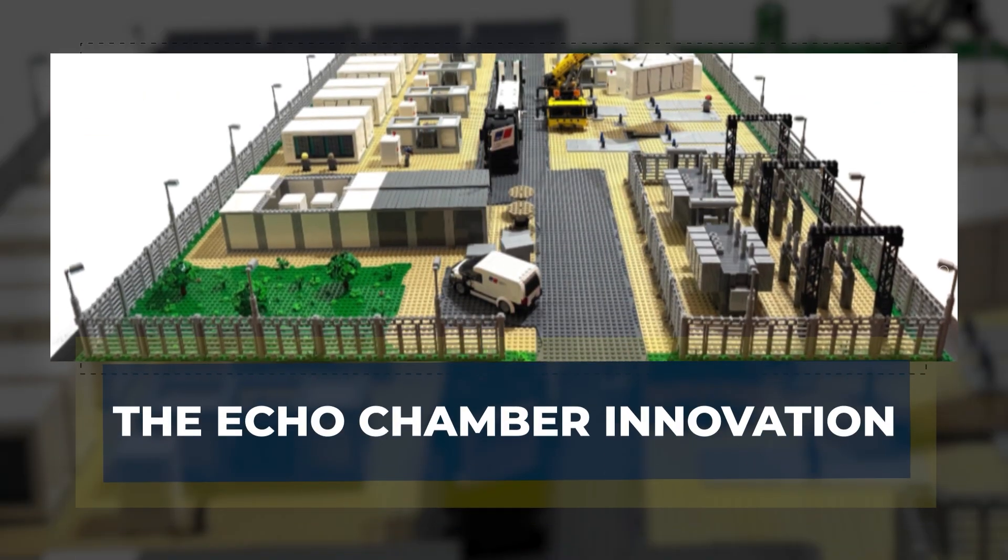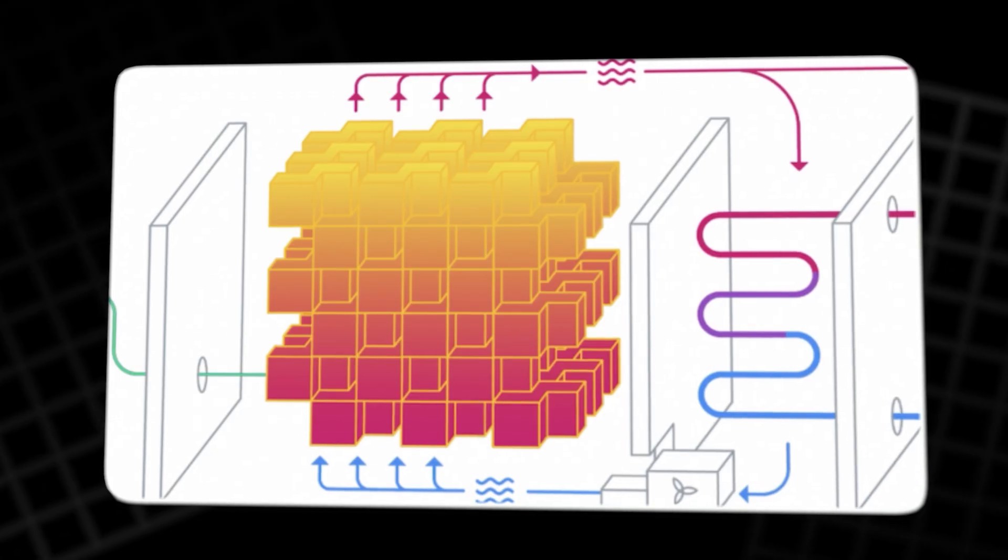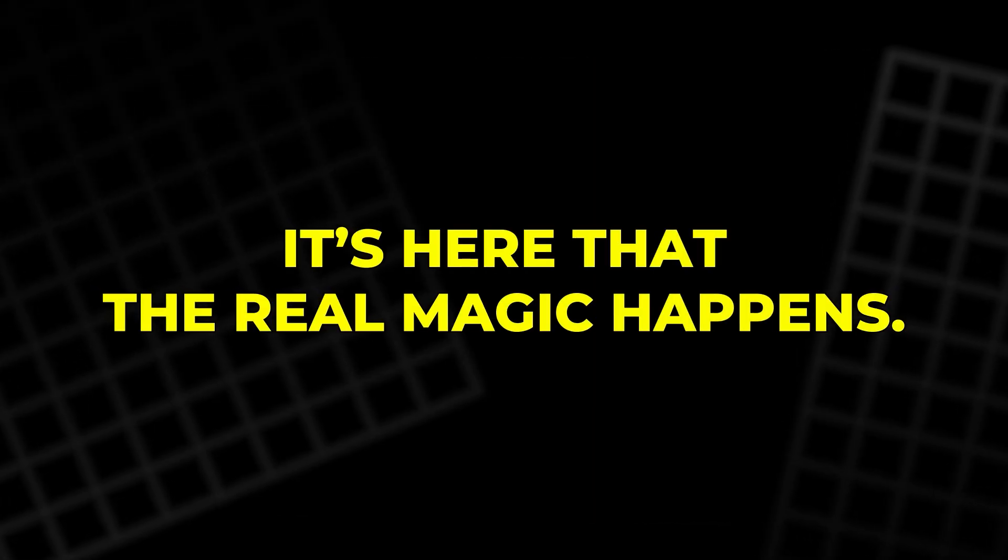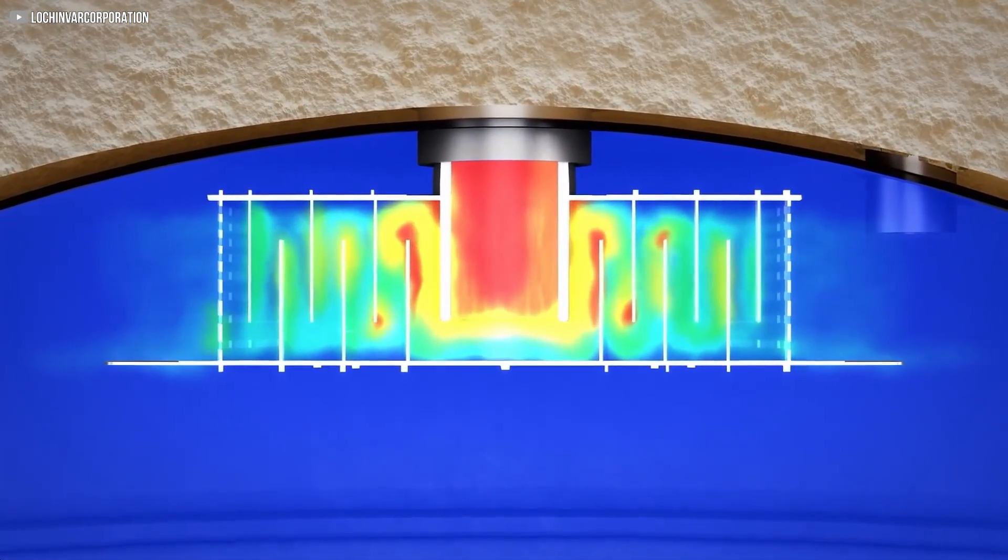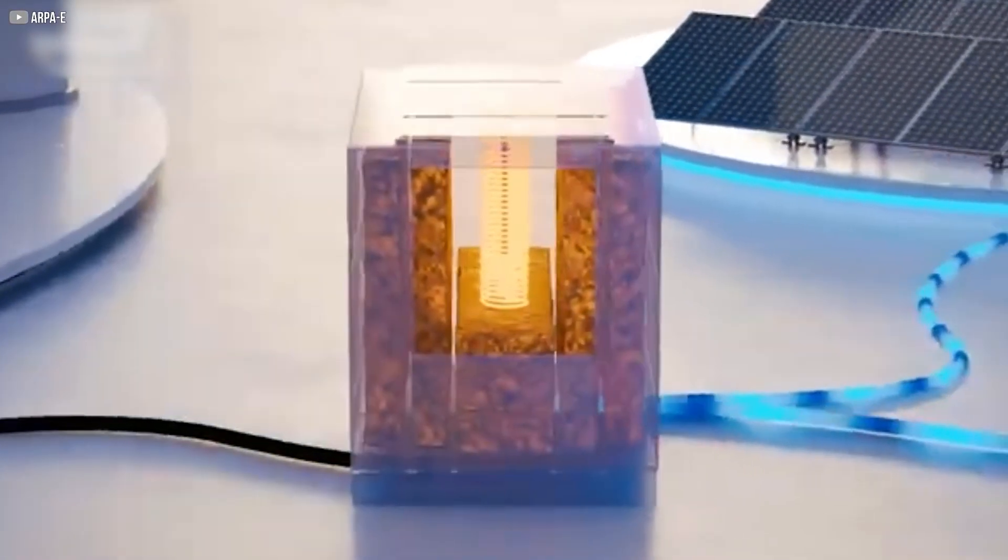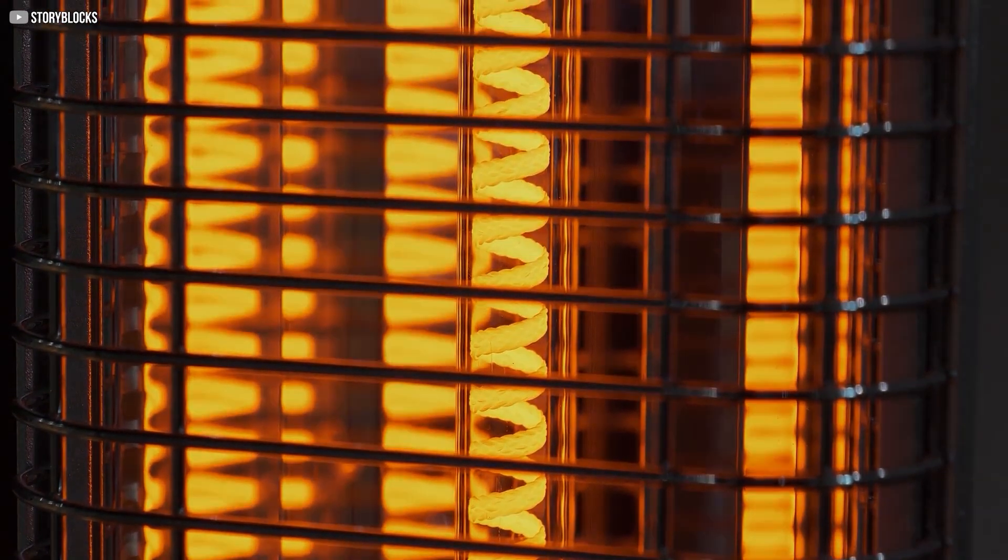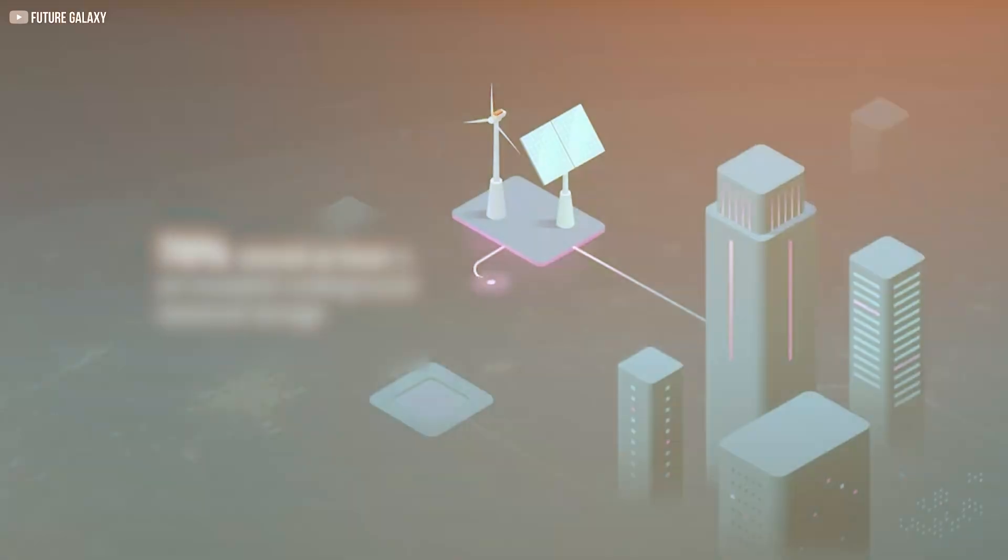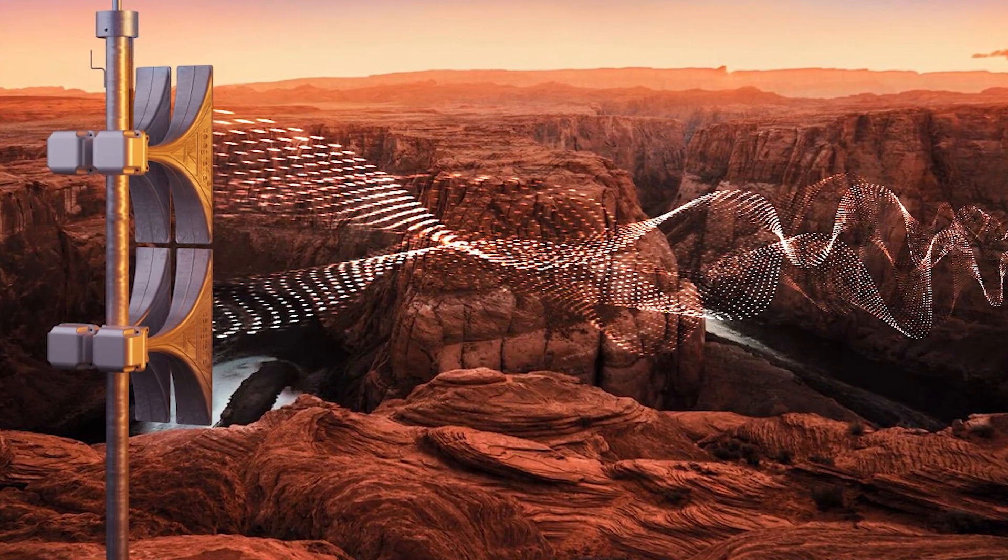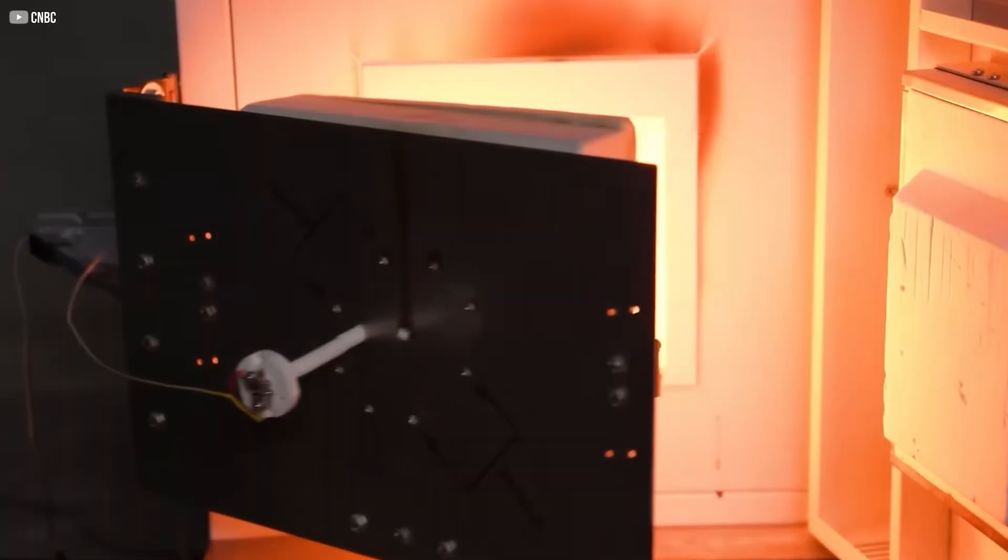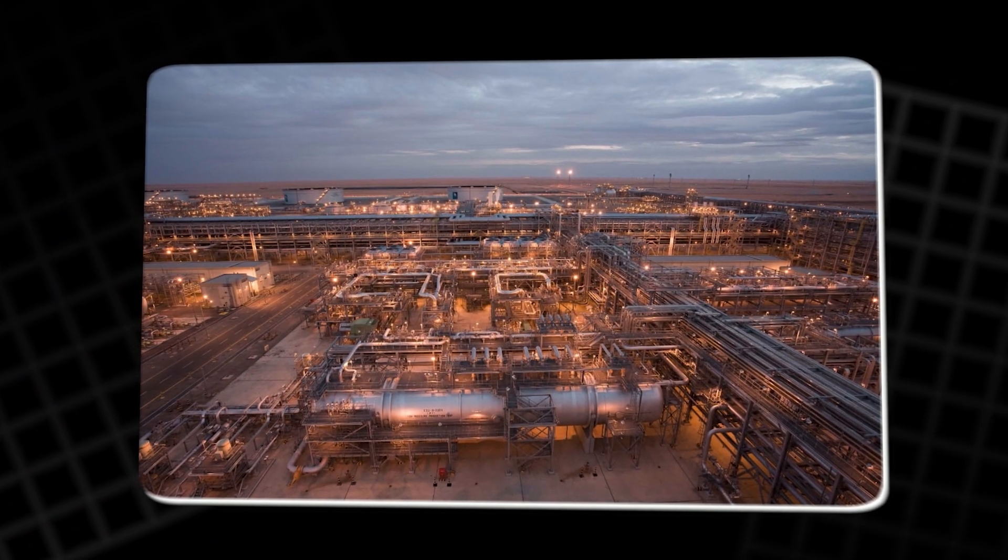The echo chamber innovation. At the heart of Rondo's system is something deceptively simple: an echo chamber made of heat. Instead of using air or water to move heat around like most thermal storage systems, Rondo uses radiation. Inside this chamber, special bricks are stacked tightly with electric heaters embedded among them. When powered, these heaters radiate heat outward, and the bricks absorb and bounce that heat back and forth, just like sound echoing in a canyon. This constant radiation allows all the bricks to heat evenly, without hot spots or slow conduction. It's an elegant fix to a frustrating problem.